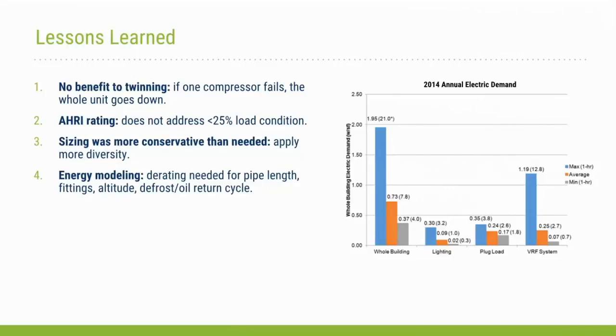Pre-modernization, just the installed lighting power density for this building was 2 watts per square foot. Post-renovation, the whole building was able to operate under 2 watts per square foot, with the VRF system contributing approximately 35% to the energy use of the building overall, with a 1-hour electric peak of approximately 1.2 watts per square foot. So a very, very efficient system.